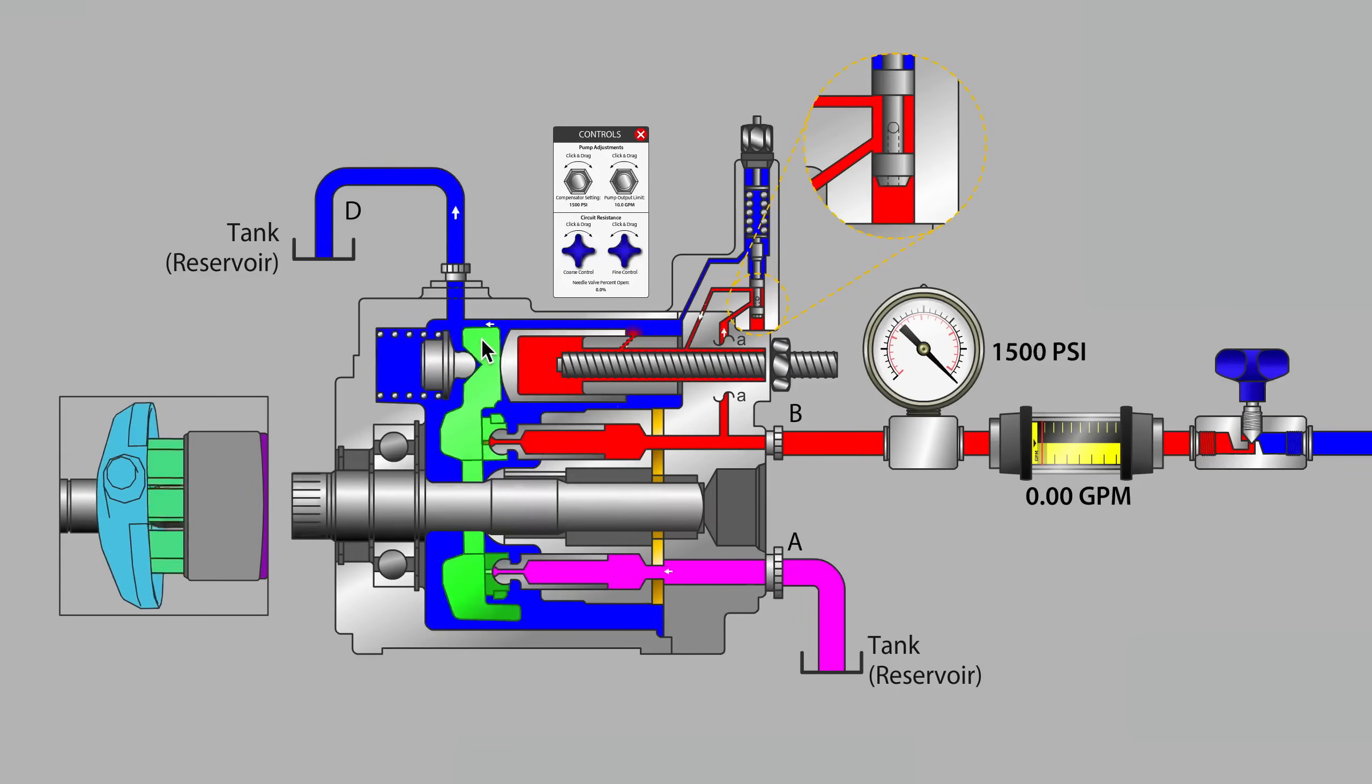The pump has gone off stroke. It's still testing to see if there is a flow path present and of course our needle valve is closed. The only flow path present is the internal leakage of clearances inside the pump.